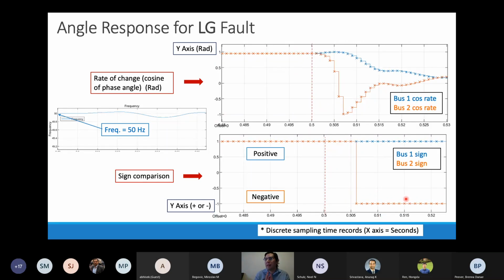Here I'm testing the same case study for a line to ground fault, and again we have the fault, and our cosine rate of change, cosine phase angle, and sign comparison help detect the fault at an early stage, in less than a cycle. As we can see in these discrete figures, we have the inception of the fault and how we are able to detect it due to the change of signal, because, as I said, the current is feeding the other way.